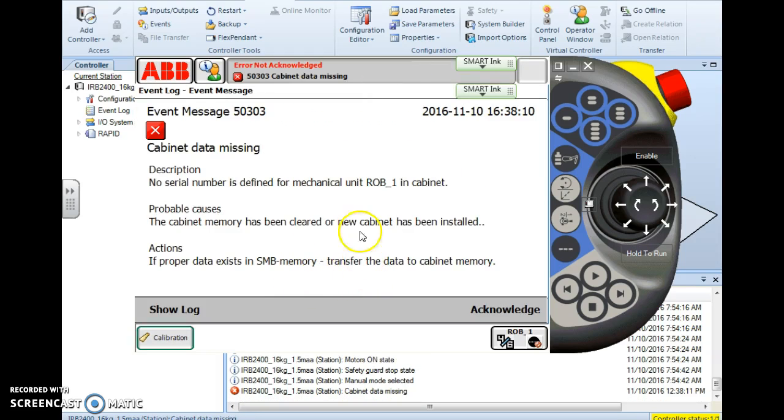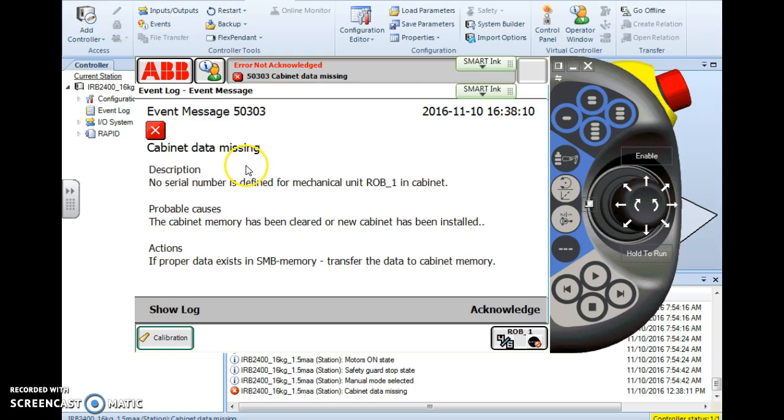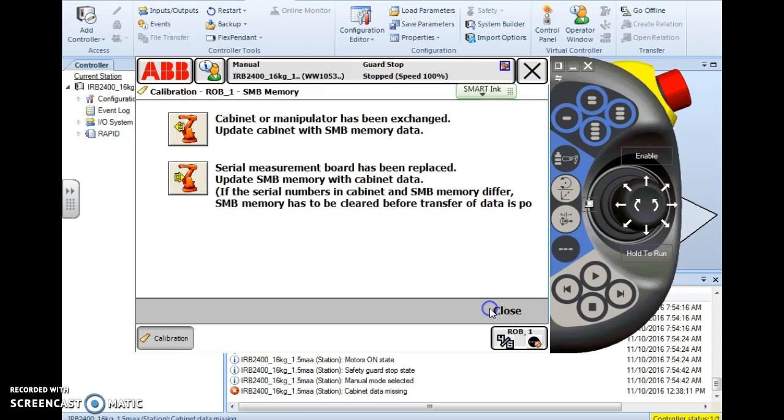At that point, as long as you're connected to a cabinet, you shouldn't get this error. But if you get this error, that means not only your SMB is bad, but your cabinet data is bad too. But if you have a functional cabinet and you know the SMB was bad and you update to it, then it should just pop up a window saying update successful.